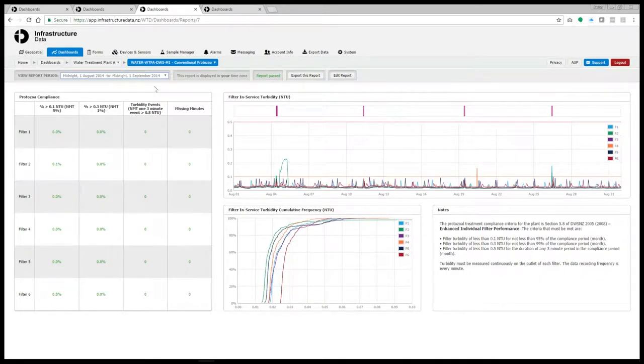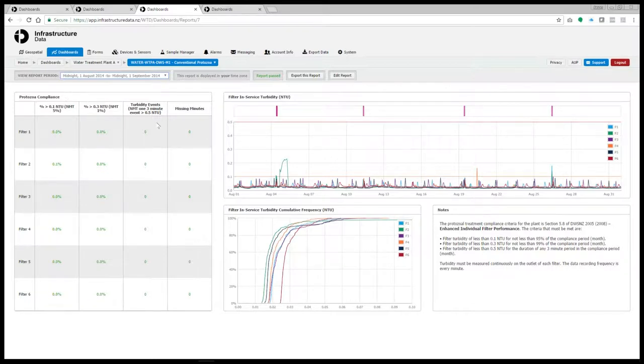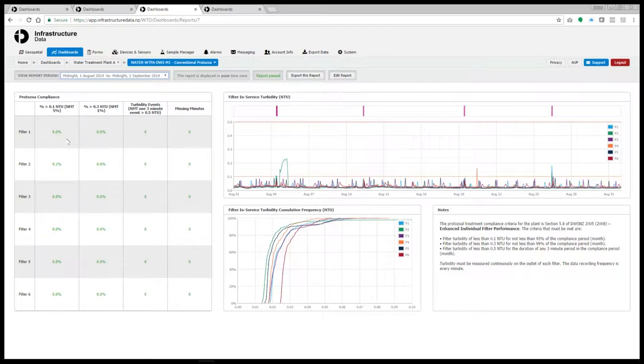This is what a Drinking Water Standards New Zealand monthly protozoa compliance report looks like in infrastructure data. We have a table over here. This has the compliance conditions for each filter for the month. This is a monthly compliance report. And everything is green. Now green is good. If we have greens across the board we are compliant and we have up here that the report has passed.